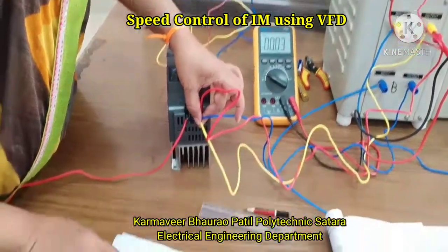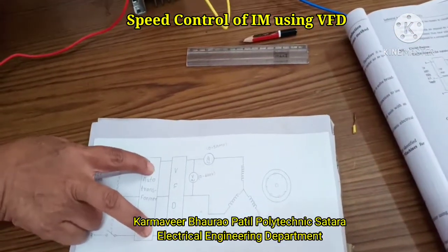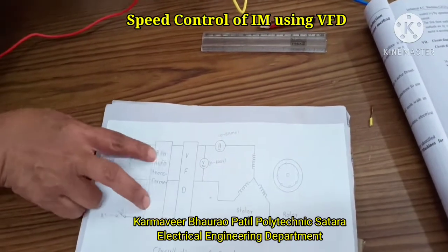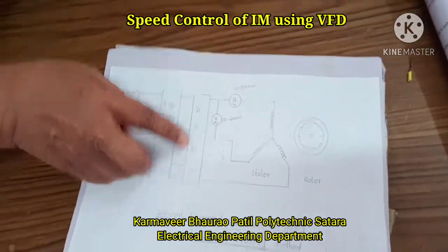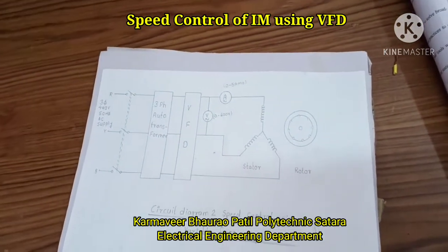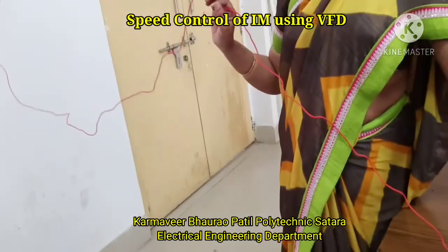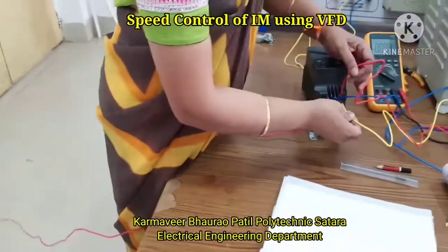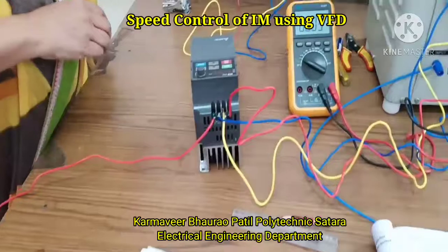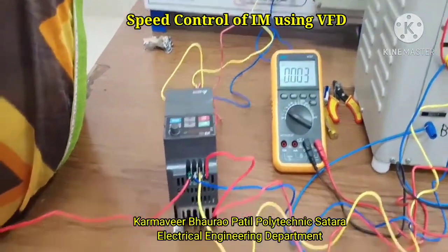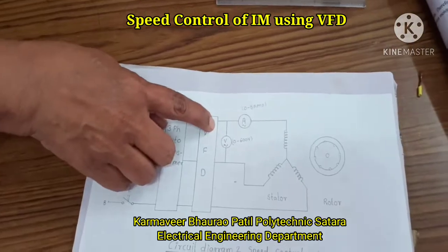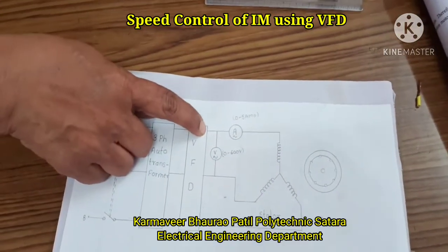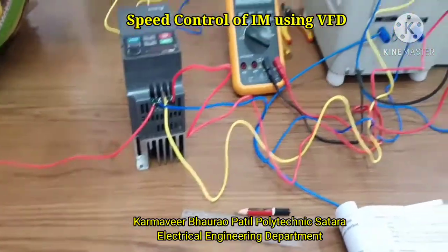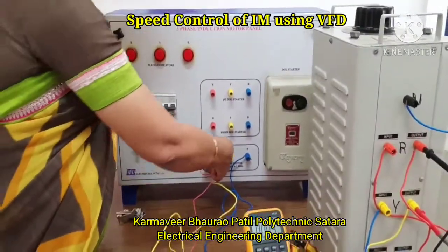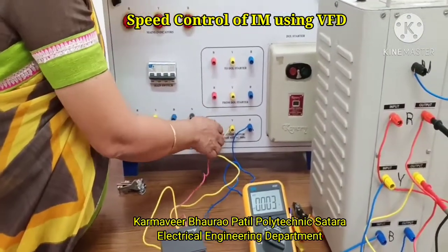The 3 supply mains are connected to the auto transformer input RYB, and the 3 RYB output terminals of the auto transformer are connected to the 3 input terminals RYB of the VFD. Only one long wire you will observe on the VFD, which you have to insert in the earth terminal. Once you connect these input terminals, what are the output terminals? Again R, Y, B. Everywhere we are using the same nomenclature, so I have not written it here. R phase of the output of the VFD will be connected to the ammeter to measure the current.